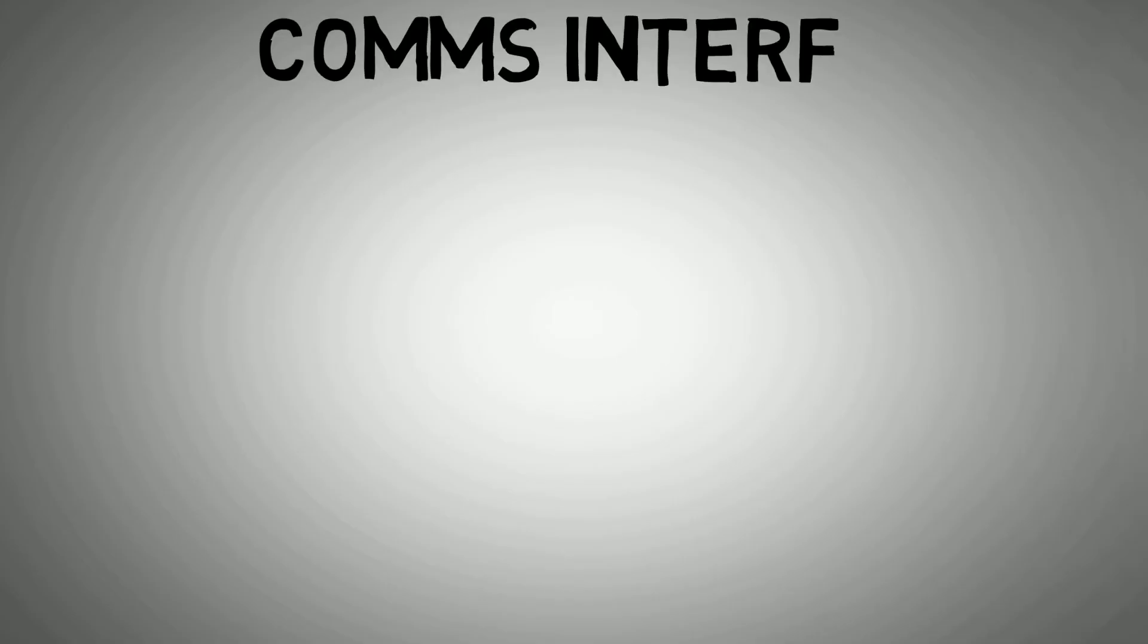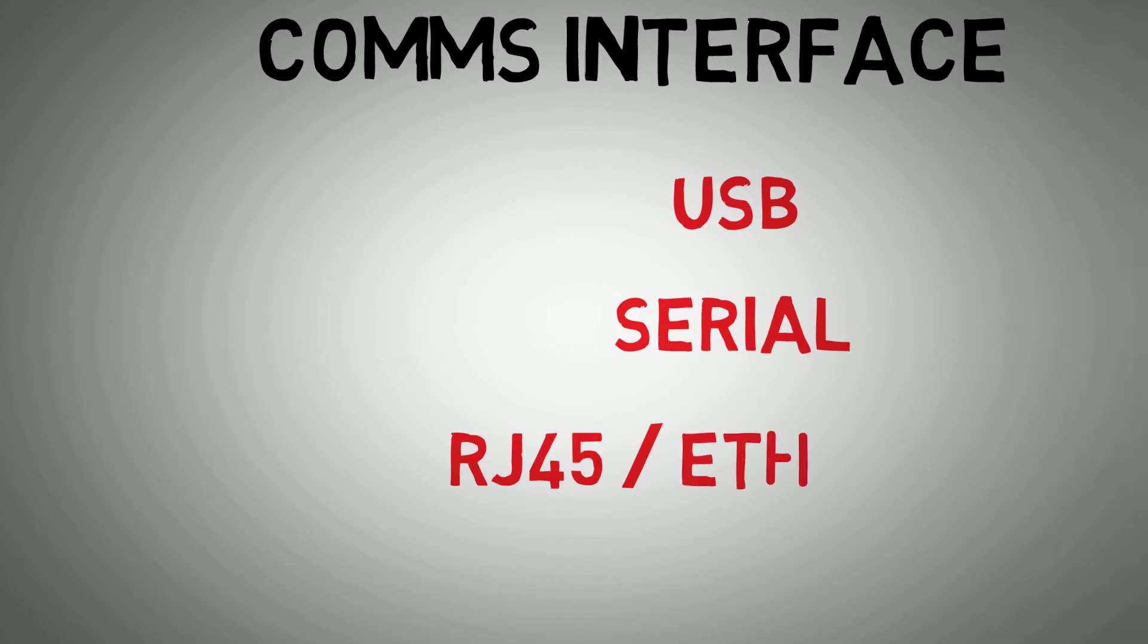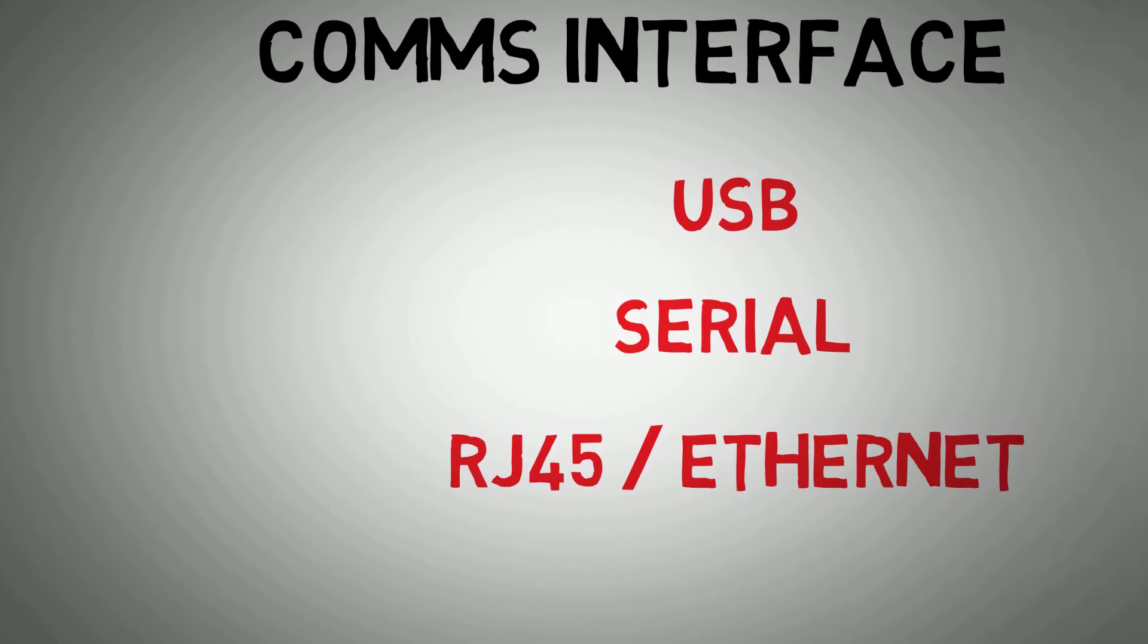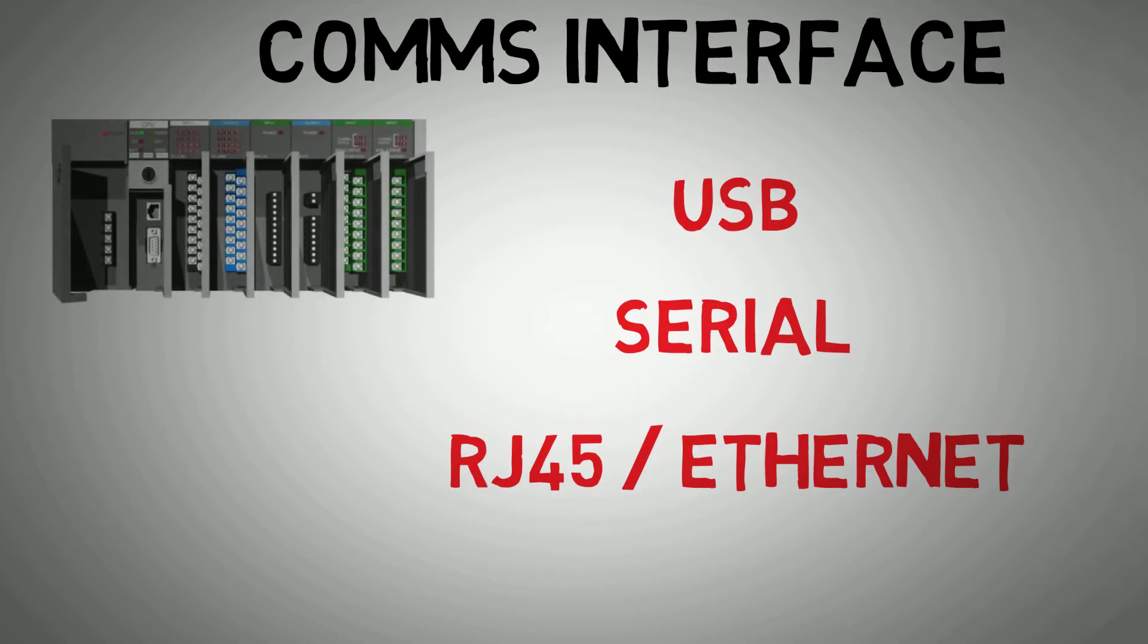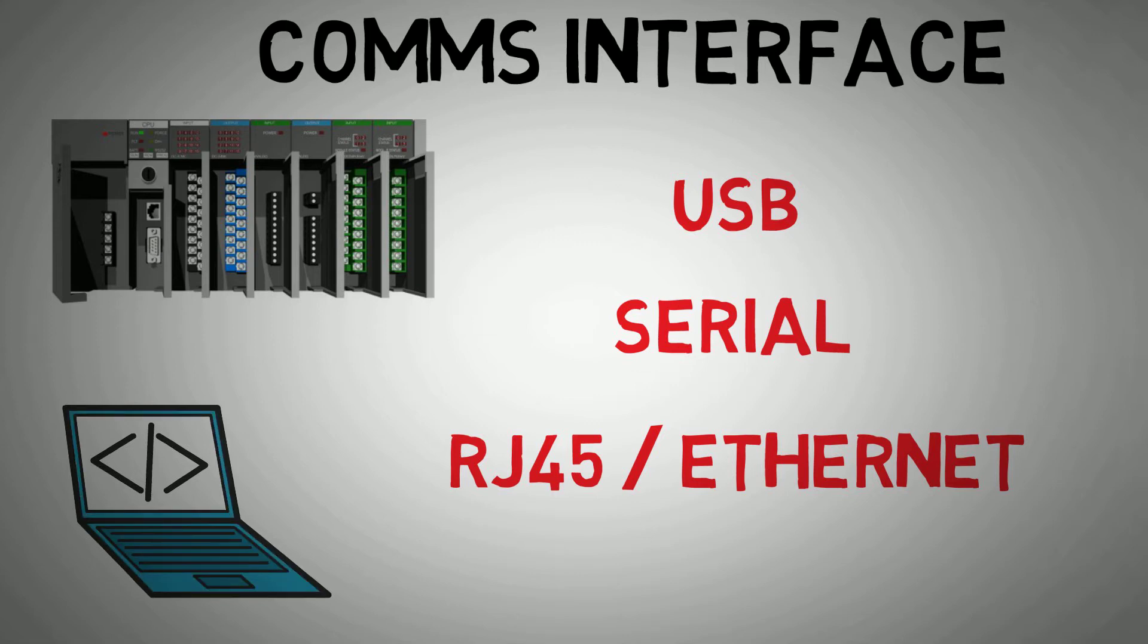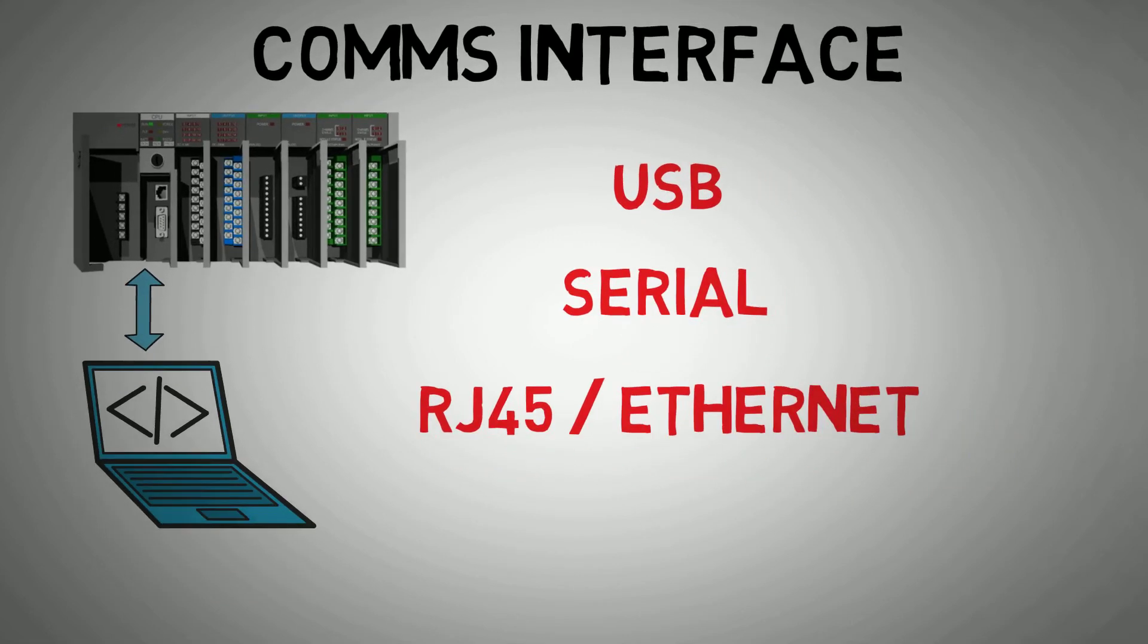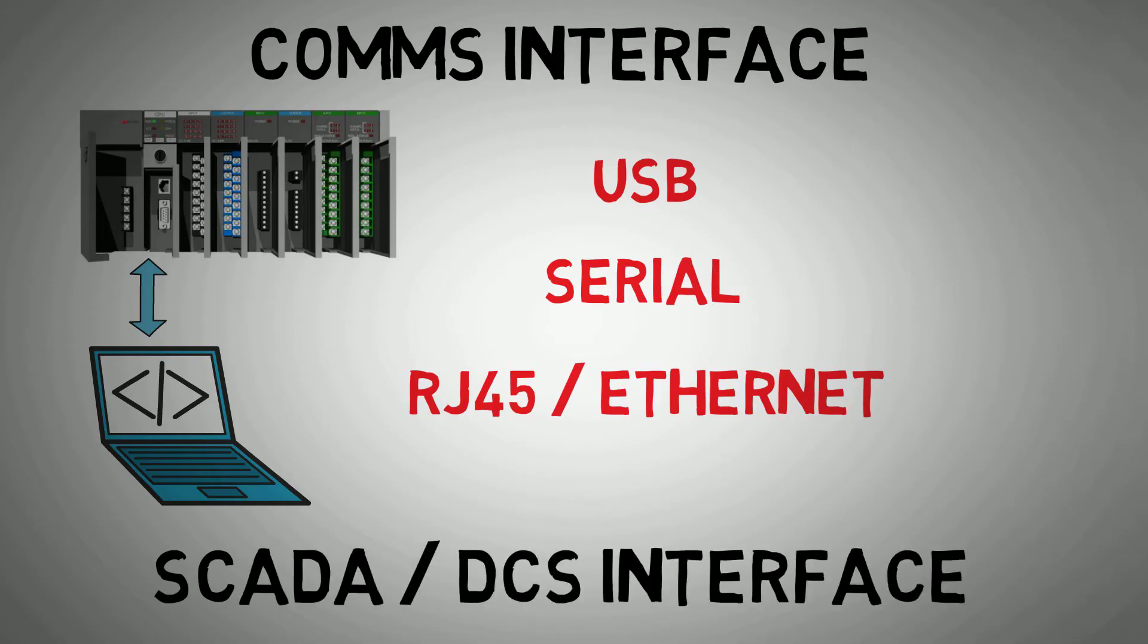PLCs will have some form of comms interface. These comms cards may be USB, serial or RJ45 connectors for ethernet connections. Comms cards will have two main purposes. They will allow interface to a laptop or server that can be used to program the software within the PLC. Comms cards can also be used to connect with DCS or SCADA for remote visibility and control as well as other remote I.O. stations.